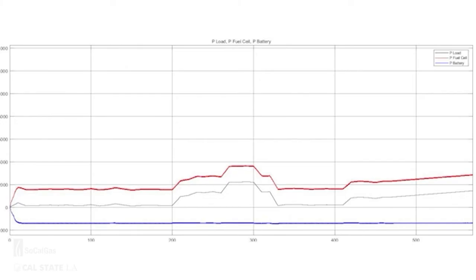The second mode is standby mode, while the station is idle between fueling operations. During standby, the backup power system does not power the compressor or chiller, and the dispenser and station draw only enough power to stay on—reaching only about 3,000 watts, much less than the fuel cell's maximum output. The battery will essentially always be recharging, allowing its state of charge to regenerate. If the battery recharges completely, the fuel cell's power output will only rise to meet the station's load.